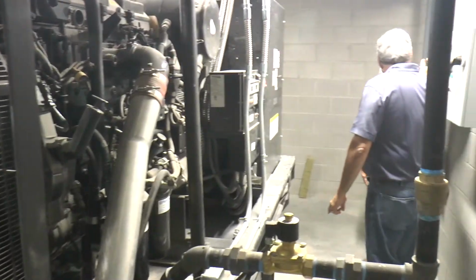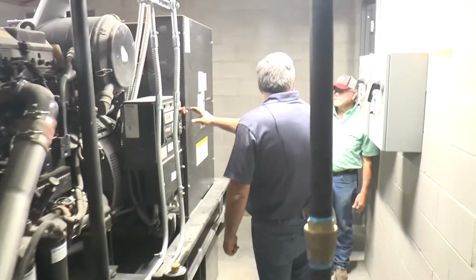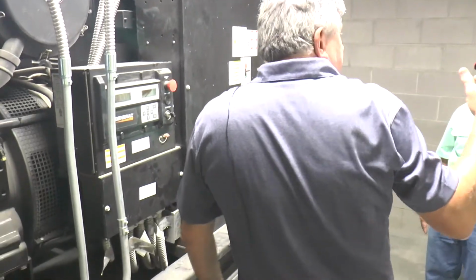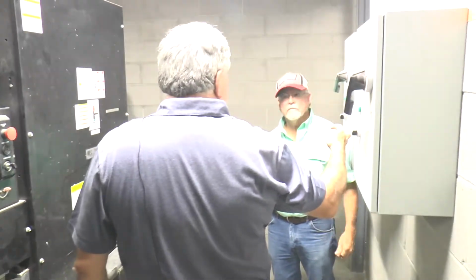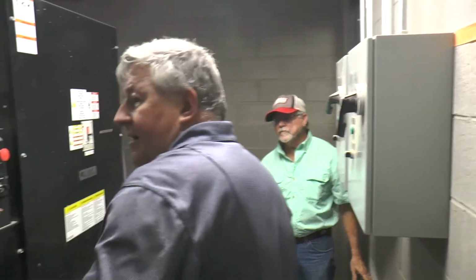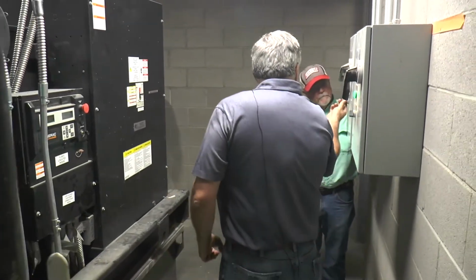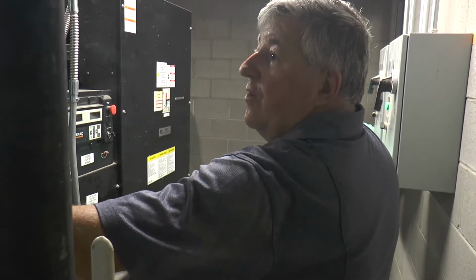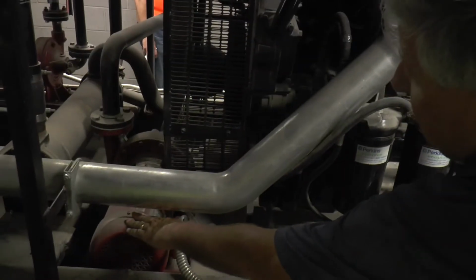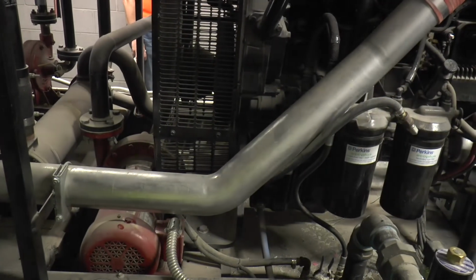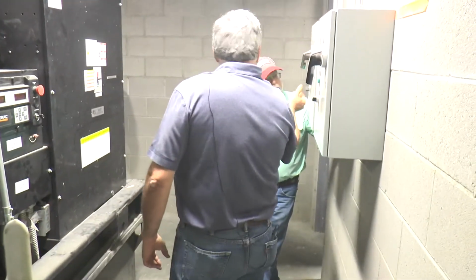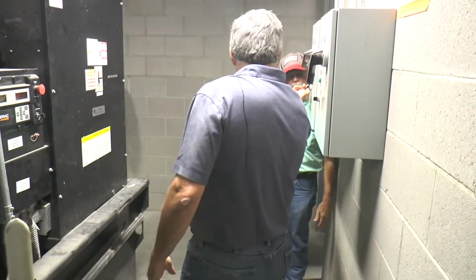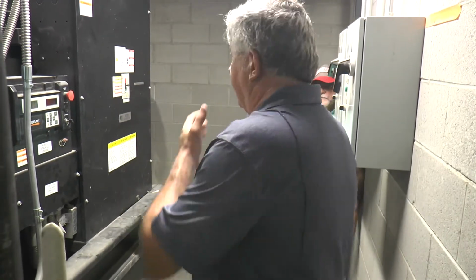These are the 2 pump controls. These pump controls run off the voltage of the generator set. In the event there's a power failure, a relay will close and tell these 2 starters to start. This circulating pump and this circulating pump is that one there and the one on the other side. You can physically turn them on. All we're doing is moving water. Okay. This one's going. So this one is moving the jacket water, which is the first pump. This one's moving the charge air cooler. Okay. So there is an air to water cooler. Since this engine is turbocharged, they cool the air that's going into the combustion system.